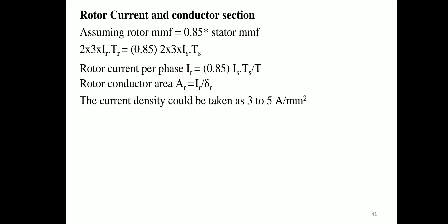Assuming rotor MMF = 0.85 × stator MMF: 3 × Ir × Tr = 0.85 × 3 × Is × Ts. Hence rotor current per phase: Ir = 0.85 × Is × Ts / Tr. Rotor conductor area: Ar = Ir / δr. The current density may be taken as 3 to 5 A/mm².